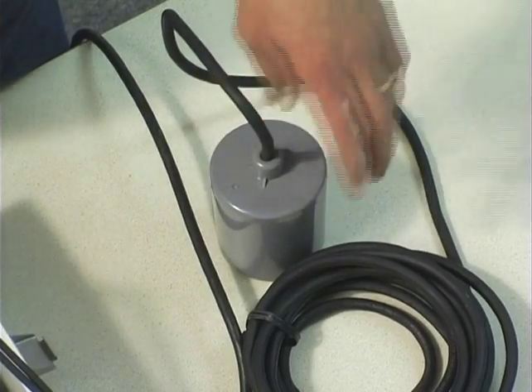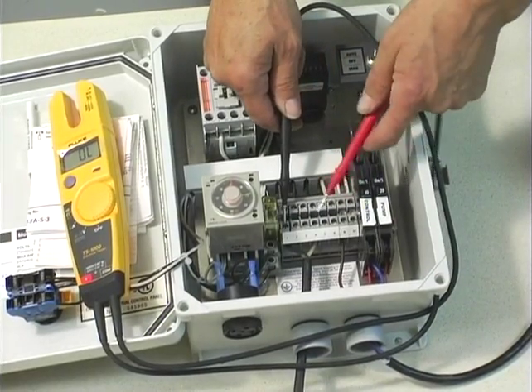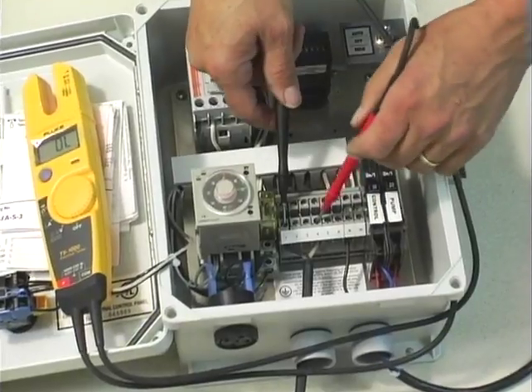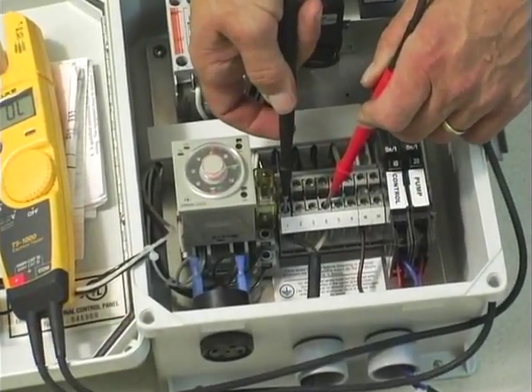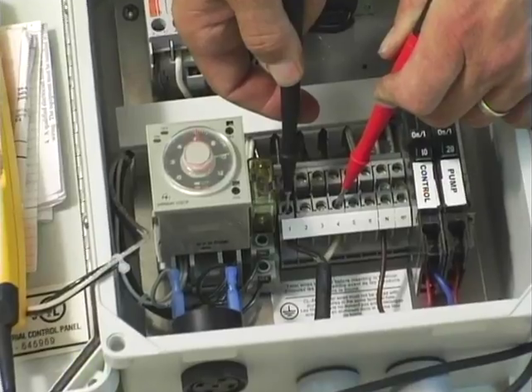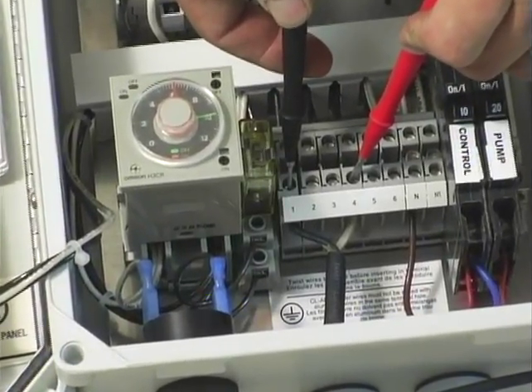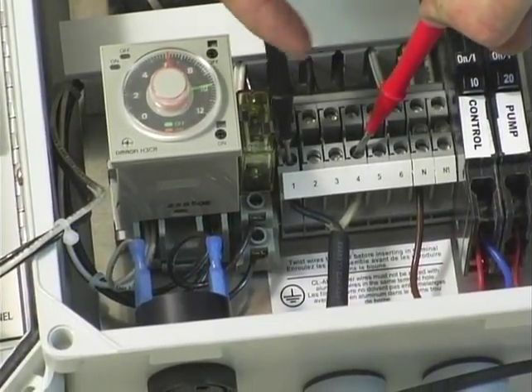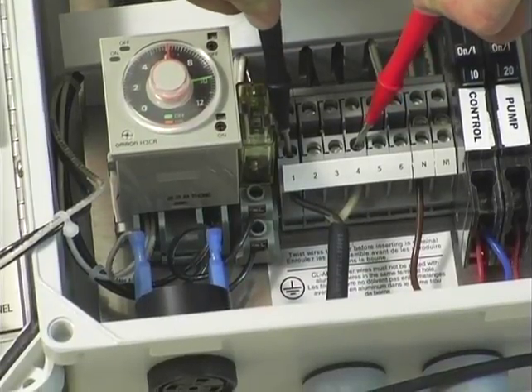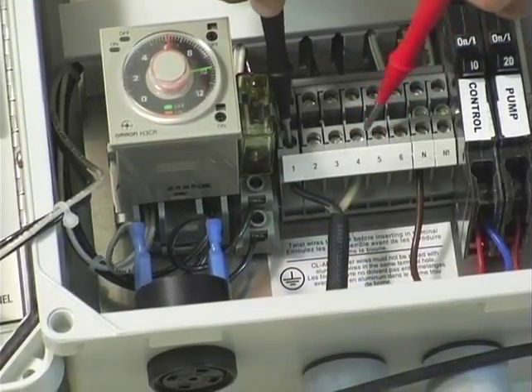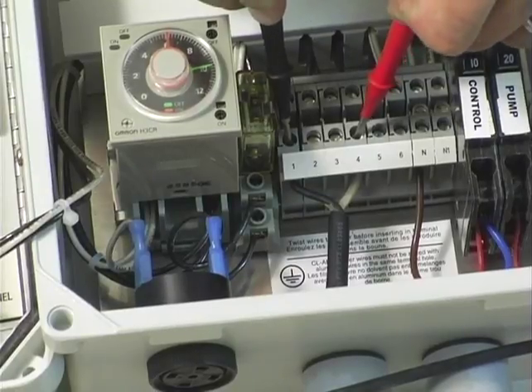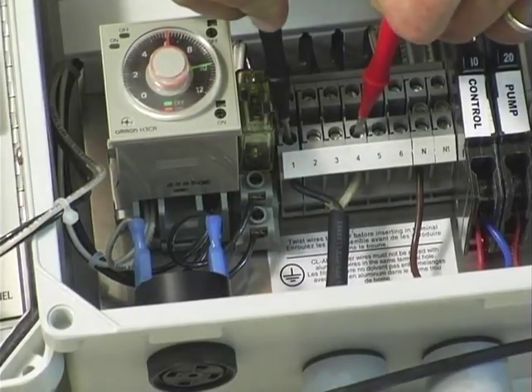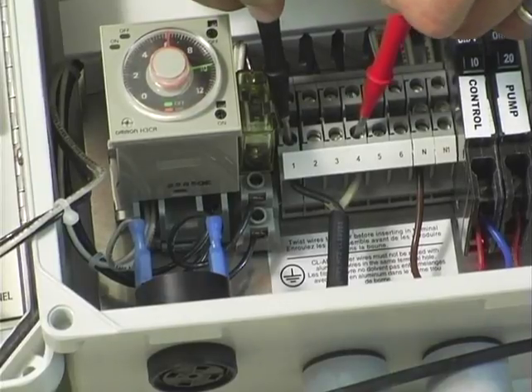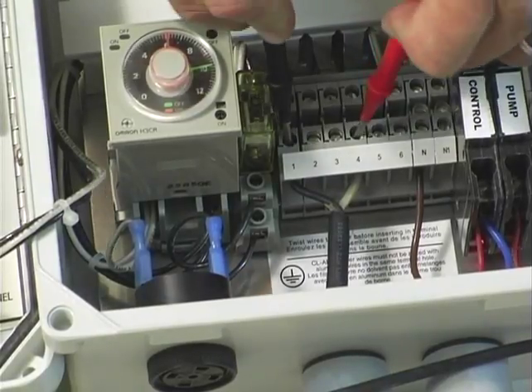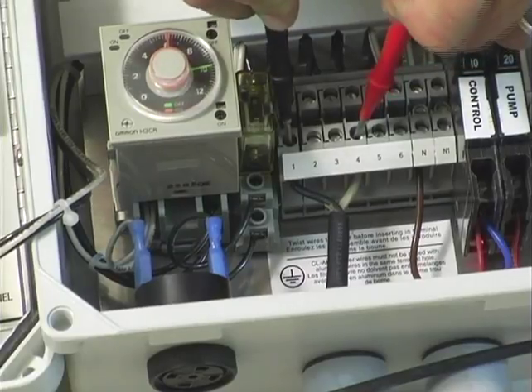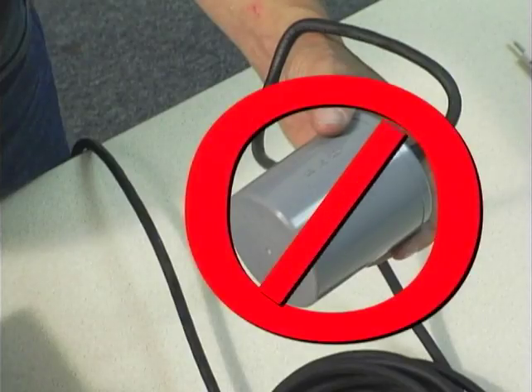Perfect. If we were to take our continuity check between number 1 and number 4 and we lifted the float and we've got an open circuit, there's two possibilities. Number 1 is there's a bad float switch or a bad wire nut out in the wet well. You can do a continuity check of the number 1 and number 4 wires just by wire nutting them together out in the wet well. That will check the wires from the control panel to the junction box in the wet well. You should get a continuity check on those. They should be a closed circuit. If that's the case, then you've got a bad float.